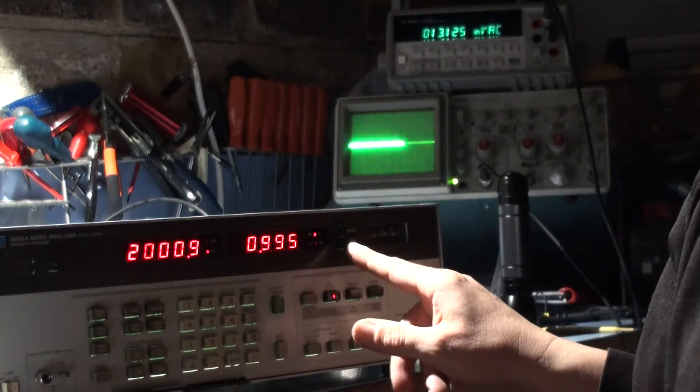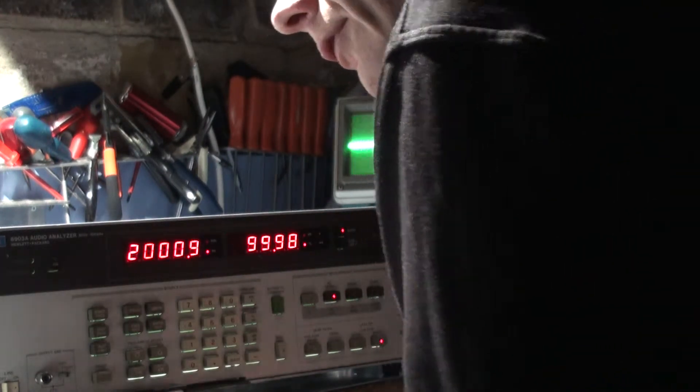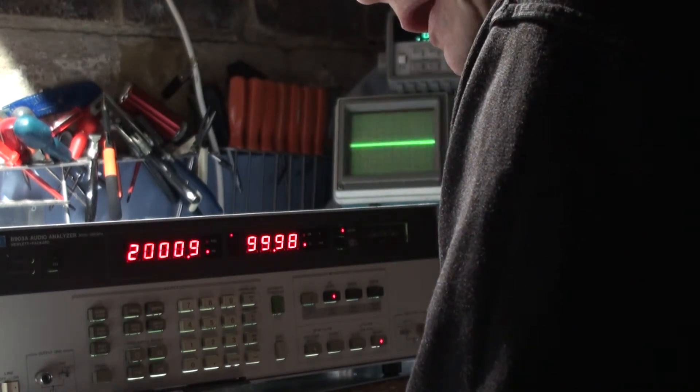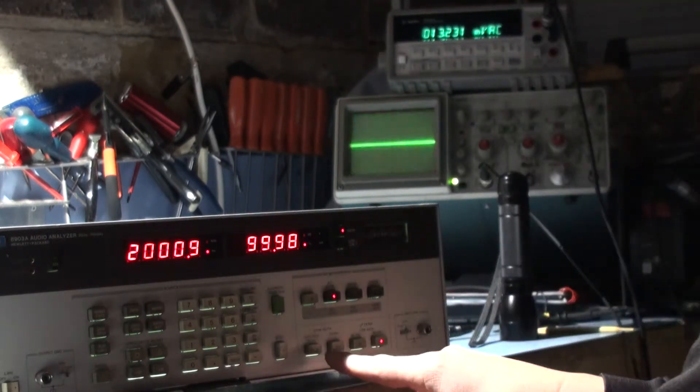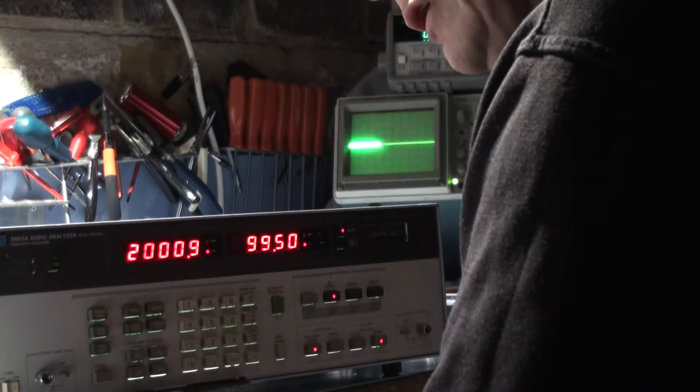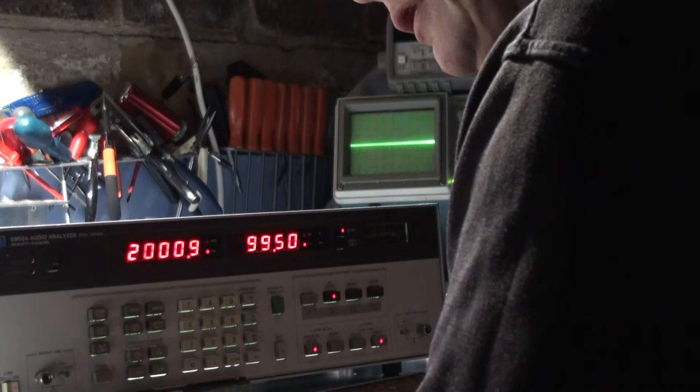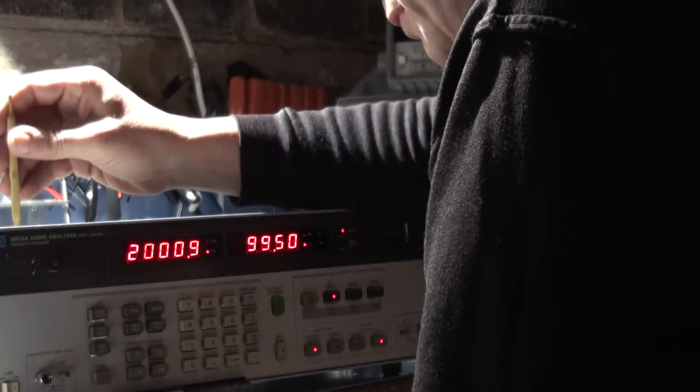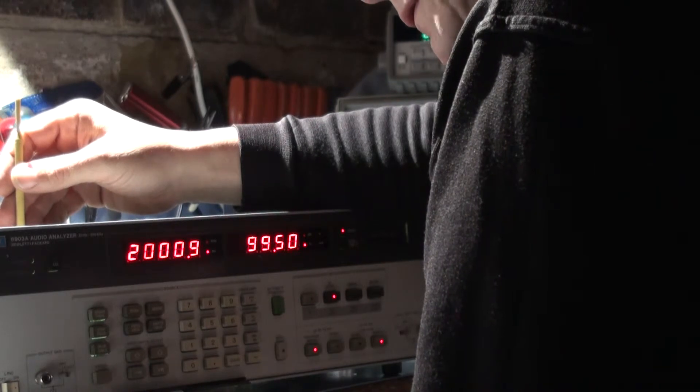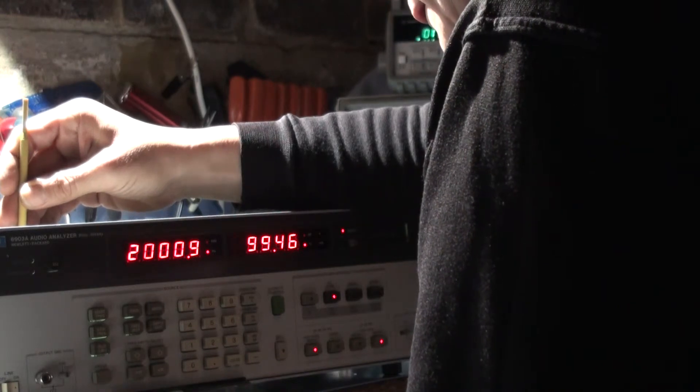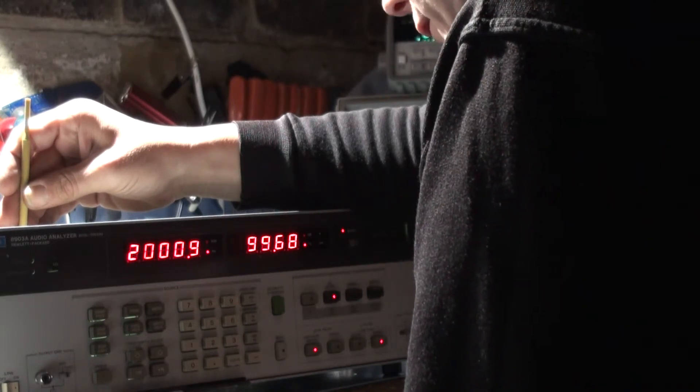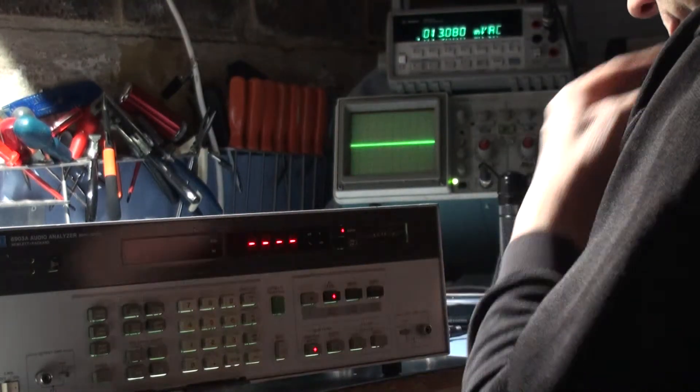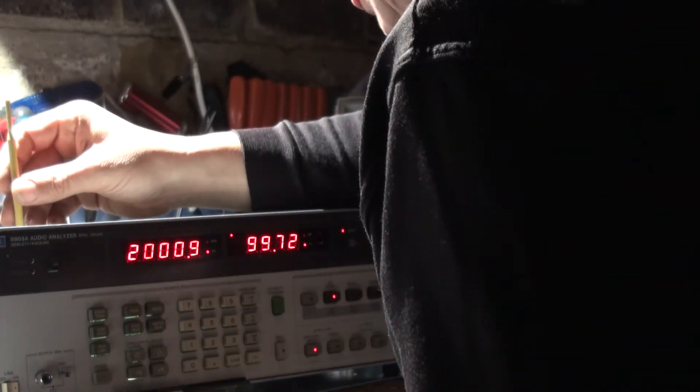Press ratio. Hold a minute, I've jumped the gun here a bit. Press the high pass button, press ratio, yes, press the high pass 400Hz. Adjust A2's R70, 400Hz, for a reading of 99.6 to 99.8 on the right hand display. It's 99.5 so it's very close. That's the 400Hz pot, so that's the one here. It's going to hardly need a touch, I shouldn't think. That's 99.7, that's right in the middle. That's pretty good.